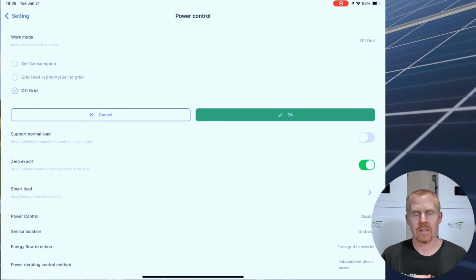If you have an AC input connection, it's going to pass all of your loads over to that connection. I kind of wish that it could be controlled a little more so you could decide whether or not you want that relay for the AC input on and off. But at the current point in time, that's not how it works. I guess it's kind of designed for if you wanted to have multiple generator connections coming into the inverter for some reason. You could use the generator smart port as an input, or you could use all your smart ports as smart loads and then route your generator into your AC input. And when power is detected on that input, then it switches all your loads over.